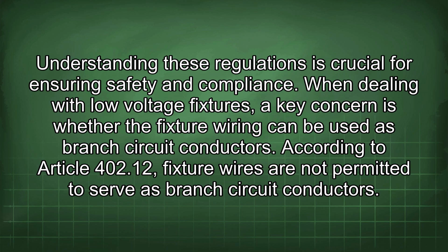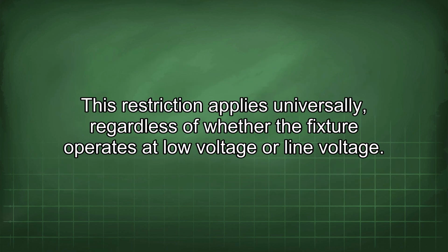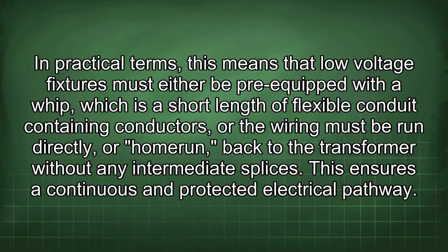When dealing with low voltage fixtures, a key concern is whether the fixture wiring can be used as branch circuit conductors. According to Article 402.12, fixture wires are not permitted to serve as branch circuit conductors. This restriction applies universally regardless of whether the fixture operates at low voltage or line voltage. In practical terms, this means that low voltage fixtures must either be pre-equipped with a whip, which is a short length of flexible conduit containing conductors, or the wiring must be run directly, or home run, back to the transformer without any intermediate splices. This ensures a continuous and protected electrical pathway.